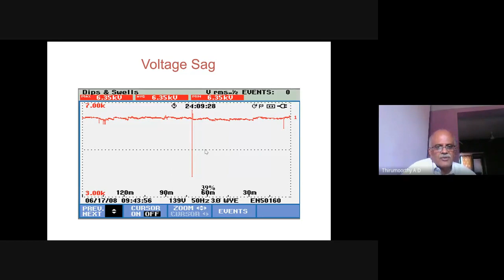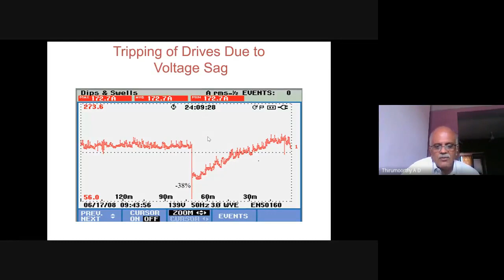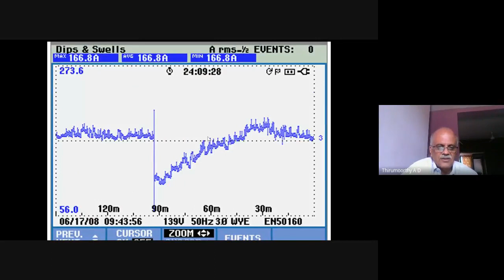During those times, this is actually a current trend that has been recorded continuously by the same monitor. You can see that at that position, nearly 38% of the variable frequency drives are tripped, and it takes nearly half an hour to 1 hour to regain the original production level. So it is an alarming situation that a small voltage sag of nearly 200 milliseconds has caused the industry to lose production for more than 1 hour. So this is typically a similar condition. You can see that a similar loss of production has happened due to voltage sag.